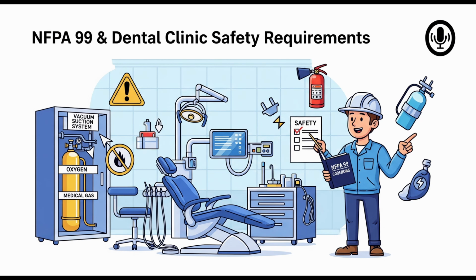What does NFPA 99 demand for these medical gas and vacuum systems, dental air, vacuum, maybe nitrous under that Category 3 designation? Sections 15.4 and 5.3 seem critical here. They absolutely are. Section 15.4 has the dental-specific rules, but it constantly points back to Section 5.3 for the general Category 3 system requirements. And 5.3, in turn, often references Section 5.1 for the foundational rules for all medical gas systems. So you kind of have to read them together. Like layers of requirements. Exactly.